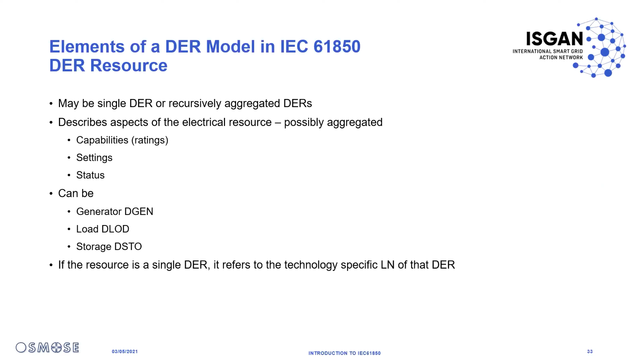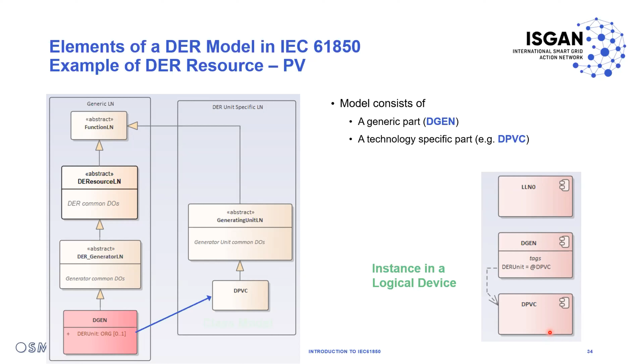This is shown on the next slide: a little example of a model of a photovoltaic system as a 61850 DER resource. We basically have a first logical node DGEN, the generic generator, where we find all the generator characteristics of our photovoltaic installation. But then we have associated to that a specific logical node, which models the photovoltaic array or system as such, where we find all the information specific to the photovoltaic device.